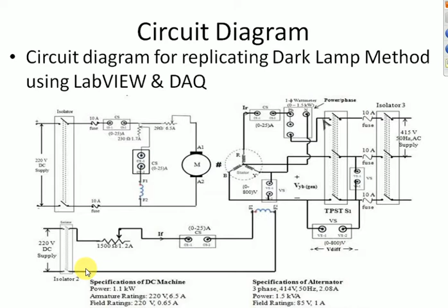This is the block diagram for the whole system. You can see that if the difference in the two voltages, from the generator and the bus, is zero, these Boolean controls in LabVIEW will glow, and then you know that this voltage difference is zero, so you close the switch. That is the electronic synchronization, part of this LabVIEW-centered lab bench for synchronizing the alternator with the mains.